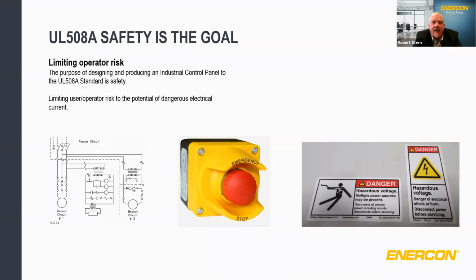So why do we design for UL508A? Well, safety, right? The purpose of designing and producing an industrial control panel to the UL508A standard is safety. Limiting user or operator risk to the potential of dangerous electrical current and limiting the potential for equipment overload and hazardous conditions that may result from the breakdown of ground, conductor overload, short circuit, overvoltage, or peak let-through current from the incoming power source. Right?